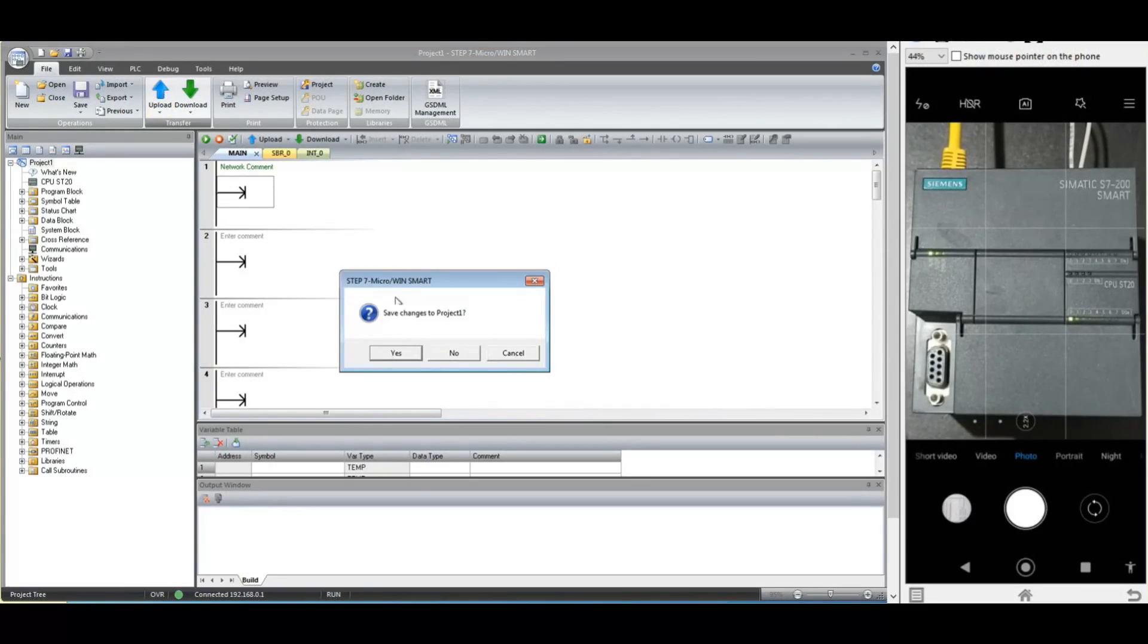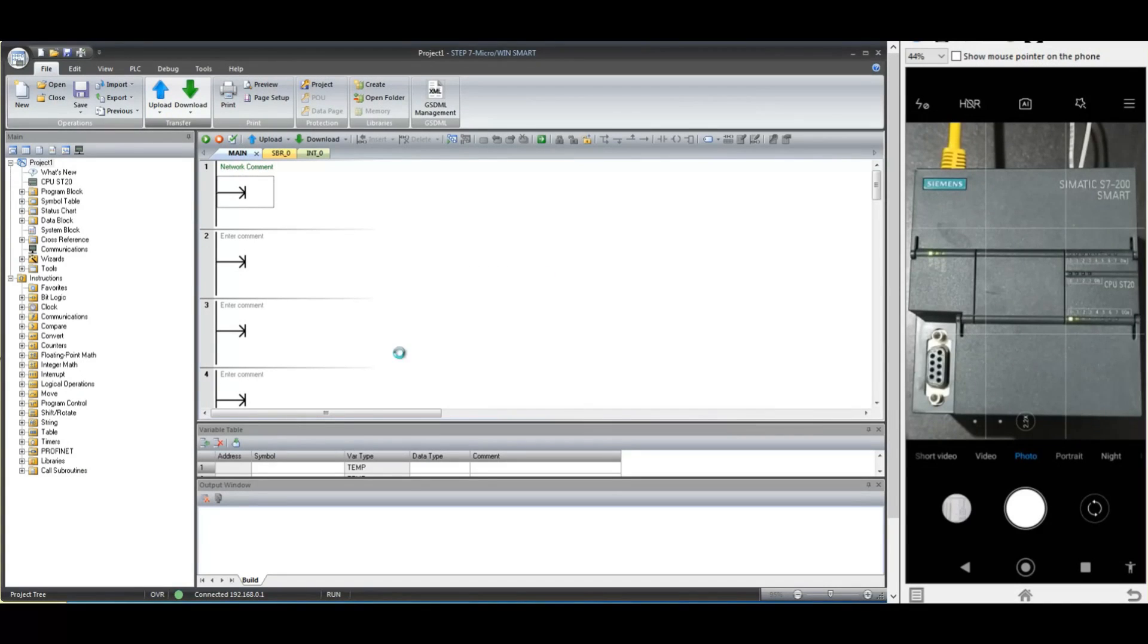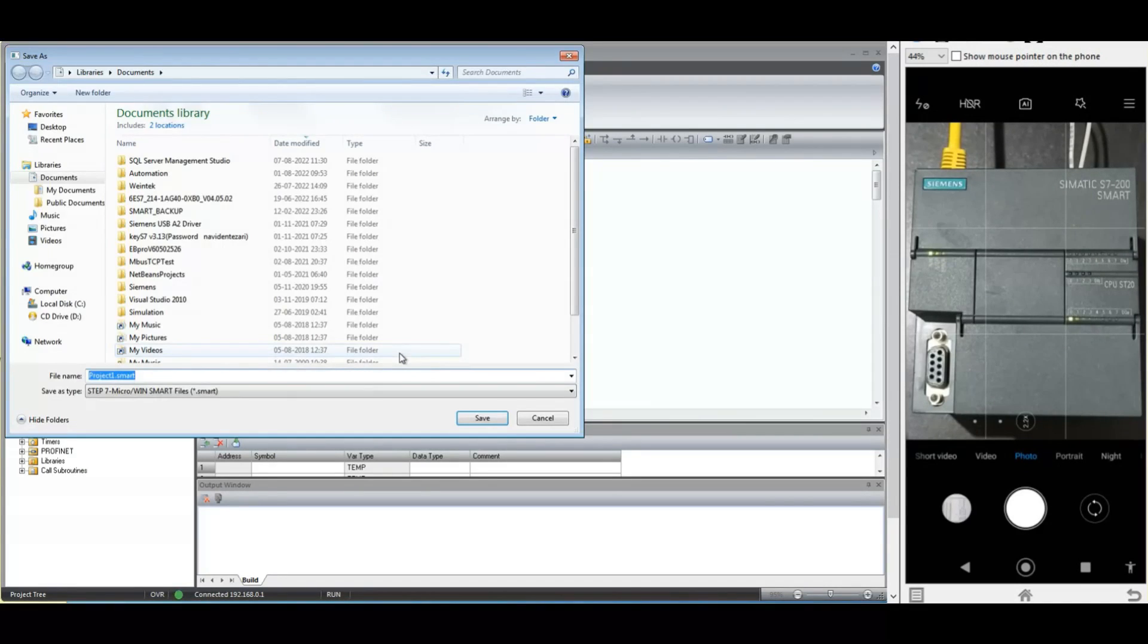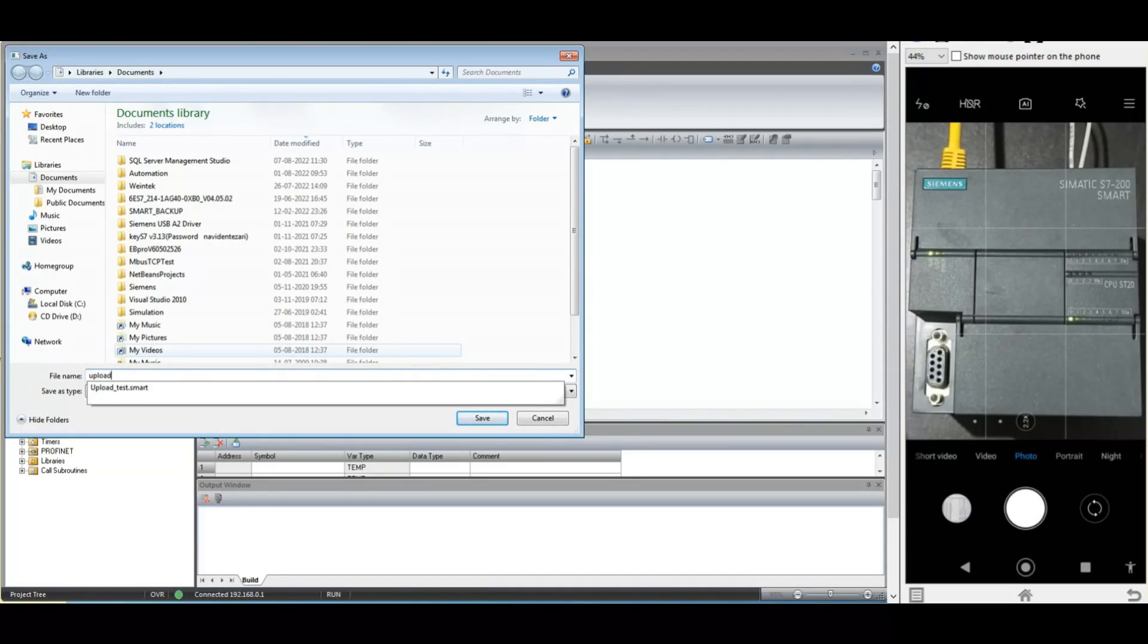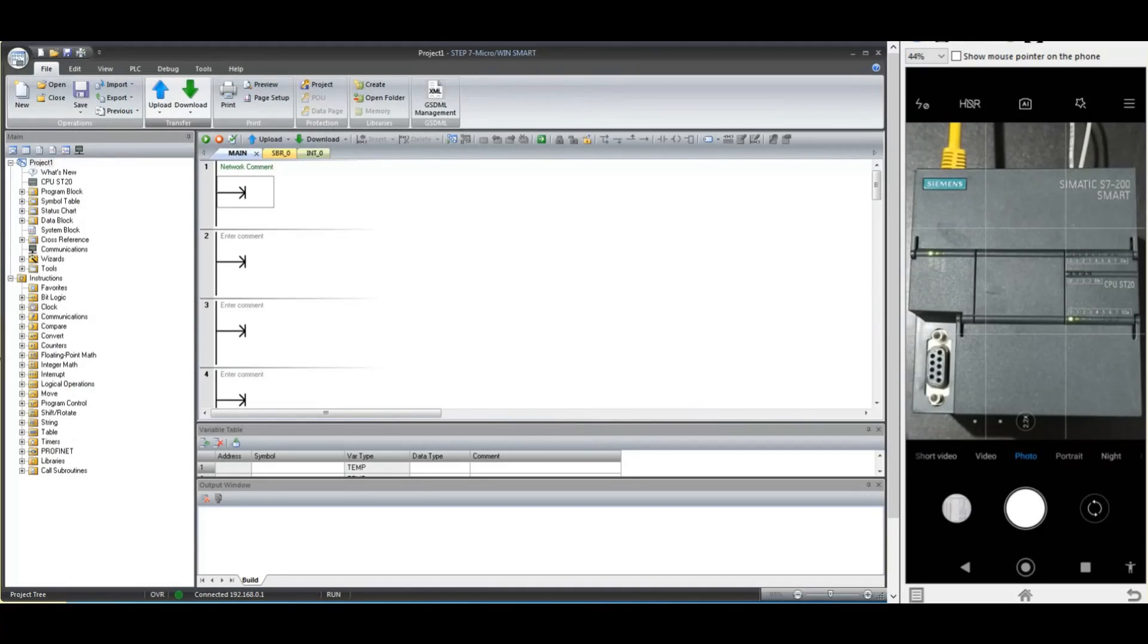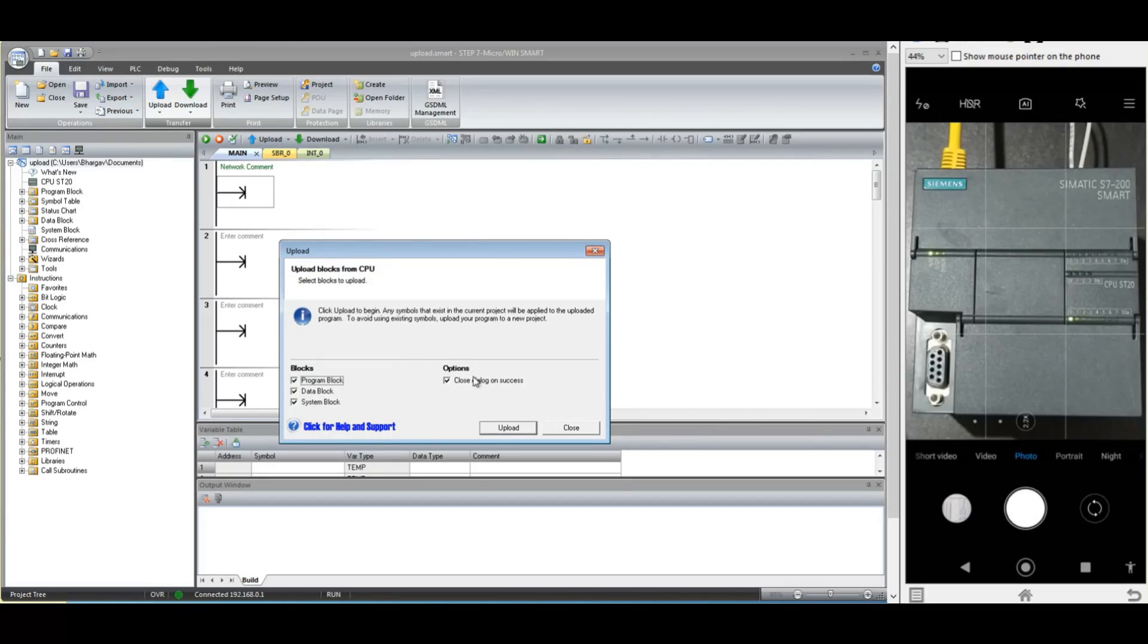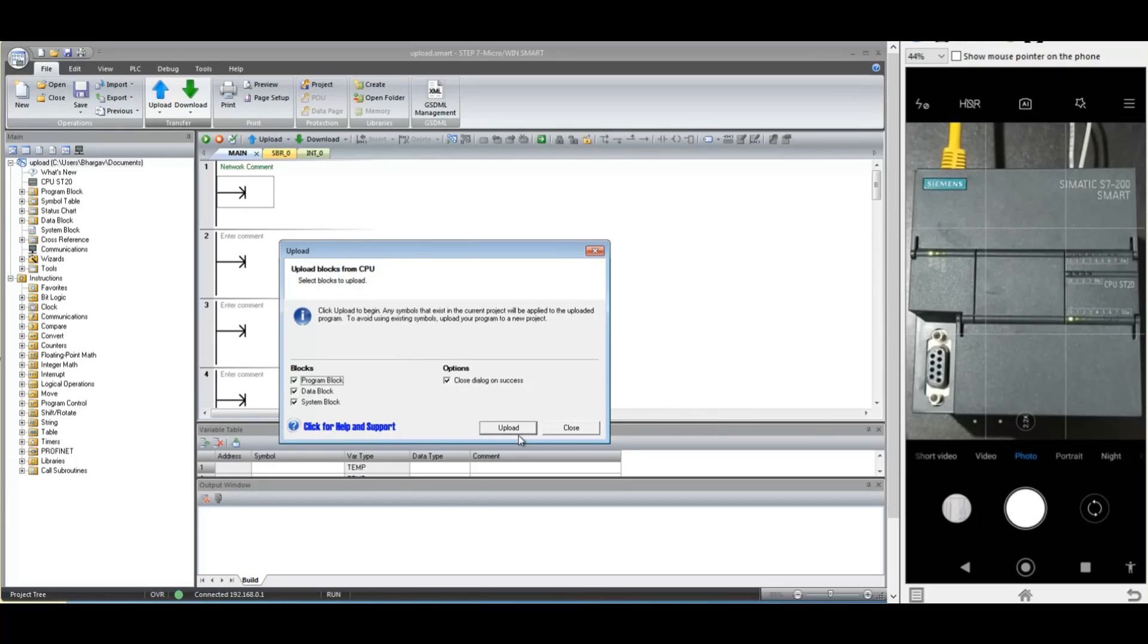Now press the upload button and software will ask you to save the backup. Save with a suitable name and click the upload button in the next window. Note that during the upload procedure, PLC will continue in run mode. That means it will not go into stop mode during the upload procedure.